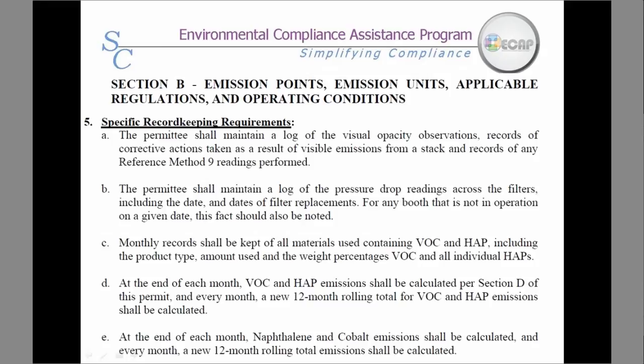Record keeping requirements — some permits will list or relist all required records, or will reference another portion of the permit that has already indicated the record keeping requirement. Records can be kept in paper or in electronic format. For example, this permit requires opacity logs, paint booth logs, material usage logs, rolling total emission calculations, and the facility also has lower limits on naphthalene and cobalt emissions due to their air toxics assessment.